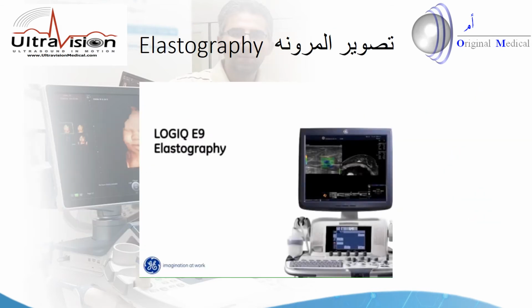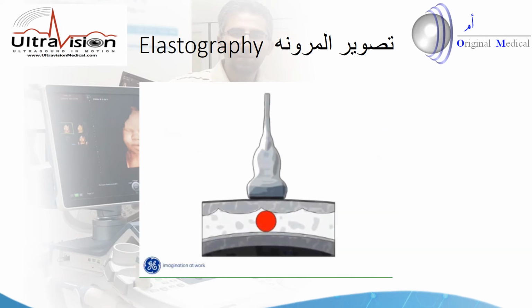LOGIQ E9 elastography. The LOGIQ E9 elastogram is achieved by positioning the ROI box around the region of interest and then applying a slight compression at the skin surface with the ML 6 to 15 transducer.